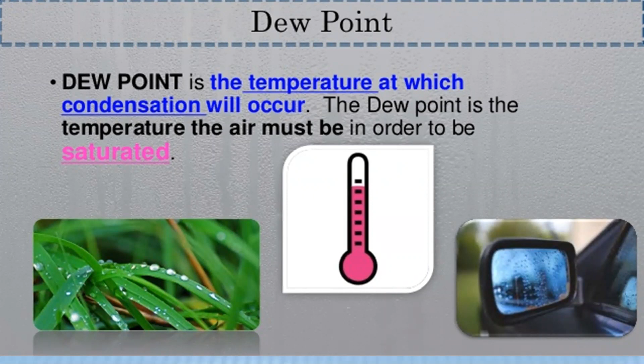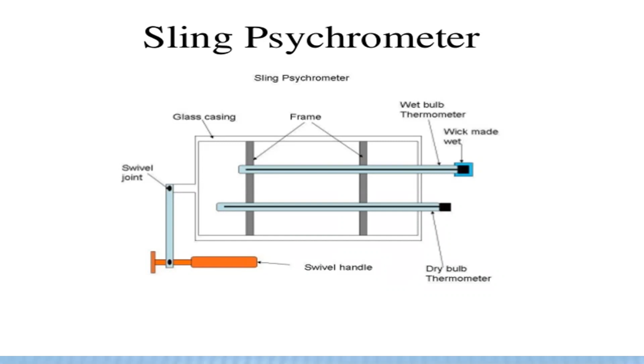The dew point is the temperature to which the air must be cooled in order to become saturated. Whether it is in a saturated position, normal position, or below 0 degrees, we can calculate the temperature. Okay, so that is a dew point meter. And a sling psychrometer: you can observe the different components in the sling psychrometer. There is a swivel joint, glass casing frame, wet bulb thermometer with wick made wet, dry bulb thermometer, and swivel handle. So the thermometers are placed to calculate the temperatures using the sling psychrometer.